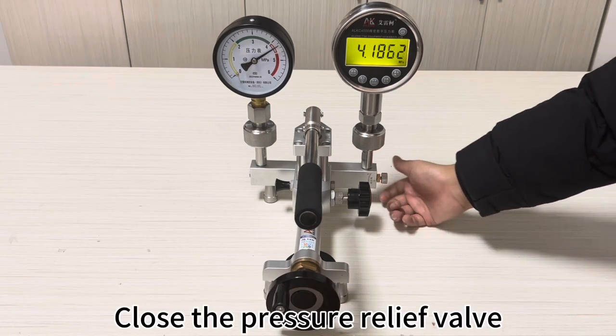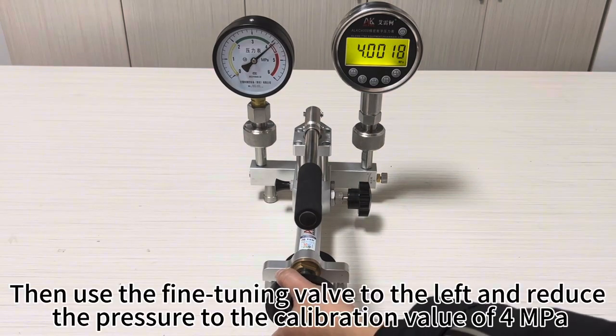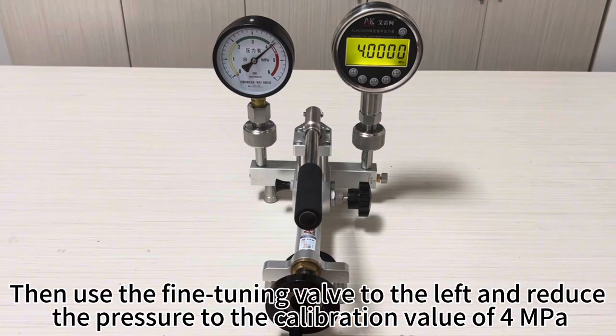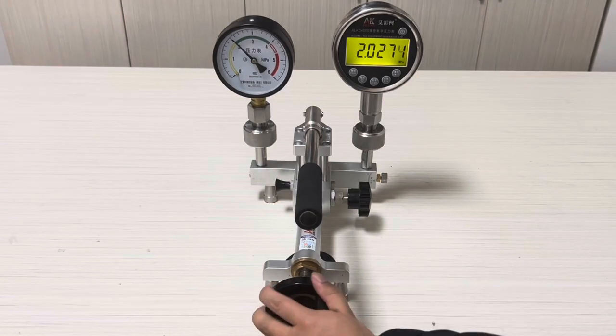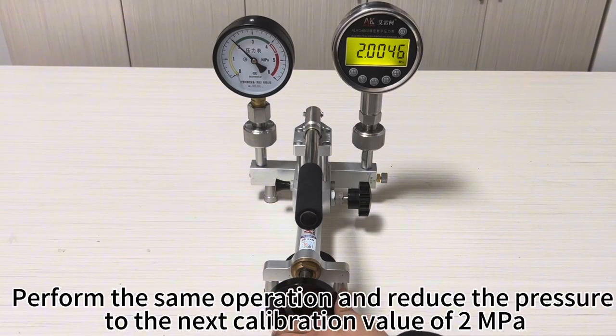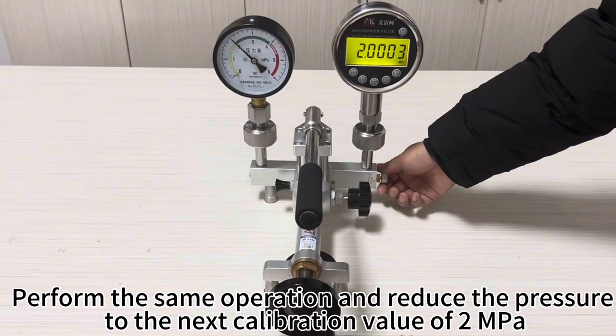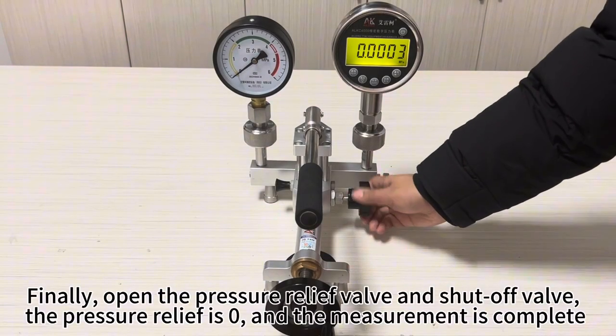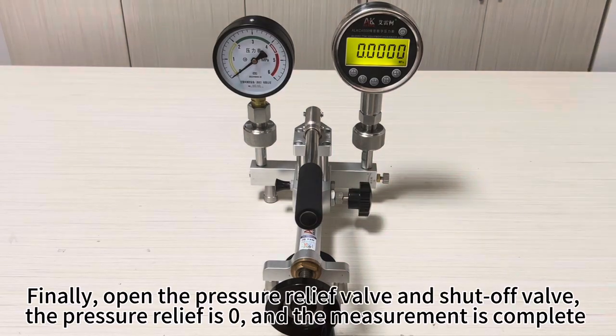Close the pressure relief valve. Then use the fine-tuning valve to the left and reduce the pressure to the calibration value of 4 MPa. Perform the same operation and reduce the pressure to the next calibration value of 2 MPa. Finally, open the pressure relief valve and the shut-off valve. The pressure reads 0, and the measurement is complete.